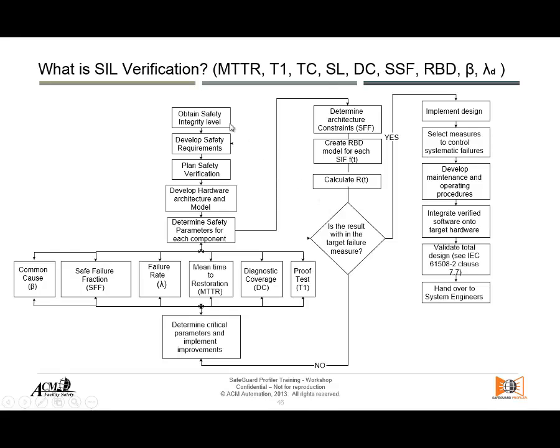Safeguard Profiler will allow you to do that. Now we go into a flowchart — a roadmap of the tasks and things we need to know first and do in order to calculate the probability of failure on demand of a safety instrumented function. The SIF is made of sensors, logic solvers, and final elements. Each equipment will have its own failure rate, each will have its diagnostic coverage depending on how intelligent it is, and we will go through each factor. We need to understand this to properly use Safeguard Profiler.